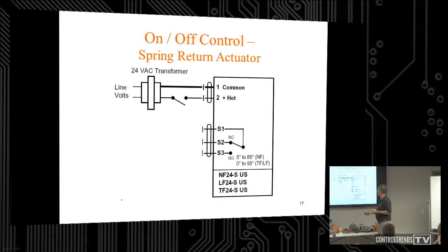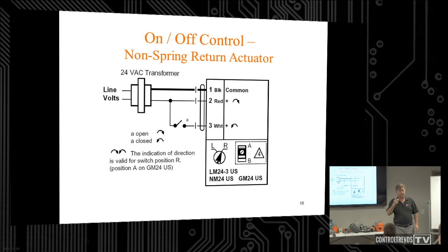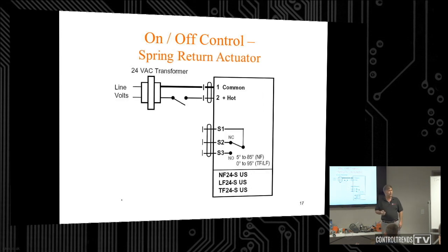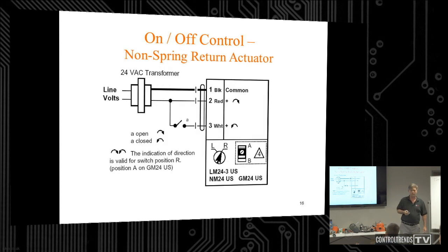Here's another example: this is one you power and it opens, remove power and it springs closed. You've got 2 wires. The first one we talked about, how many wires did it have? We had 3 control wires. So with 2 control wires we've got 2-position spring return; with 3 wires, this would be floating, correct?